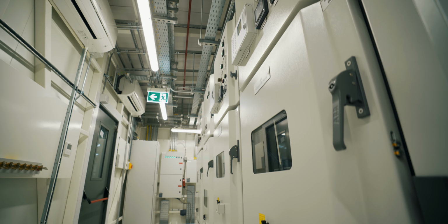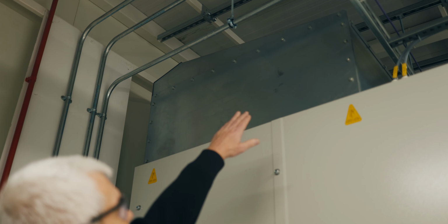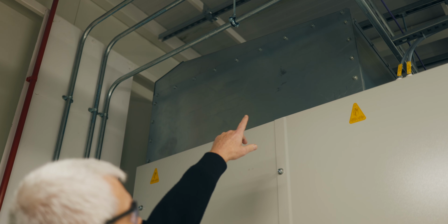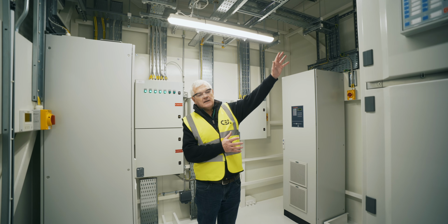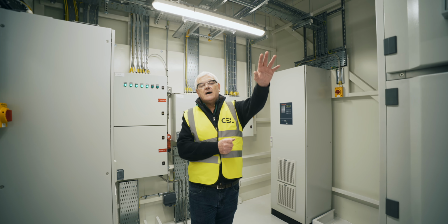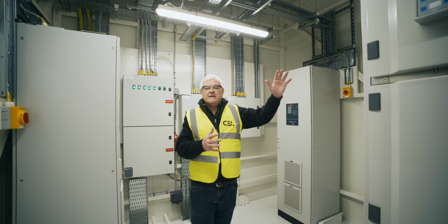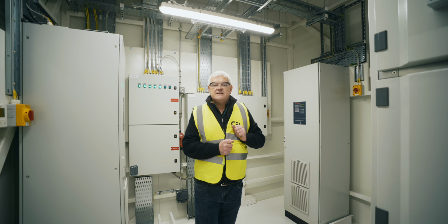So the ABB switchgear at this point has an internal arc flash control system. So the arc is controlled and absorbed in the panel above the gear and does not exit the pod. The pod also has a pressure relief valve for any pressure built up during an arc flash incident.